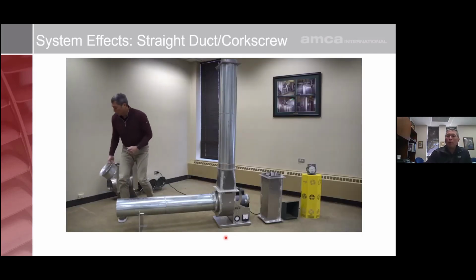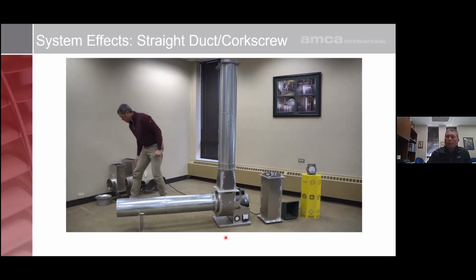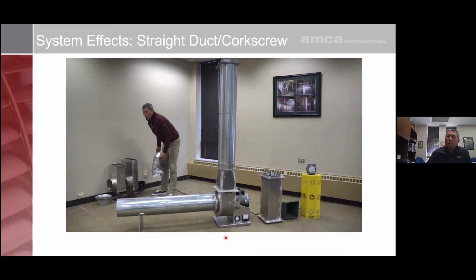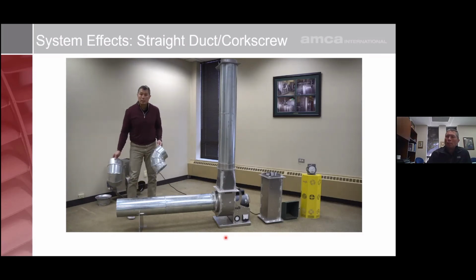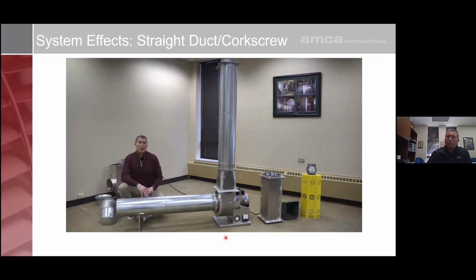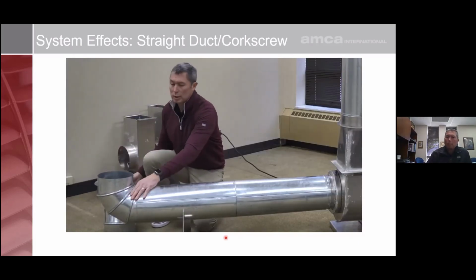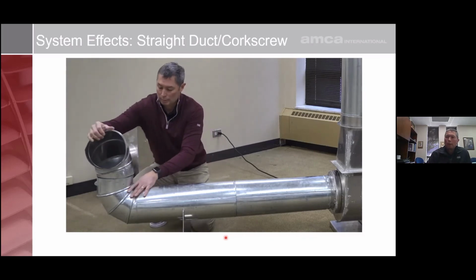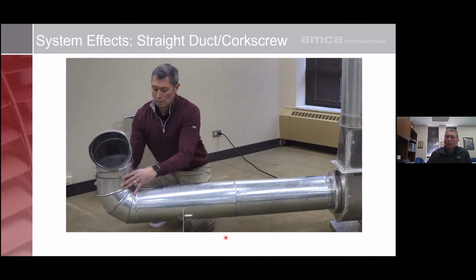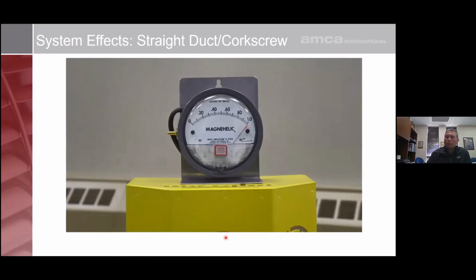Now the final thing I want to show you is corkscrews. And the problem with corkscrews is that corkscrews can go down a piece of ductwork for an extended period of time. The fan itself wants to create a venturi or a vortex as the wheel rotates. And if we create a vortex over here, that vortex will continue down that straight run of duct. And if you look at the magnehelic, you see that the losses were almost the same as the losses we saw in the first part of the video when we put the corkscrew right at the inlet of the fan.